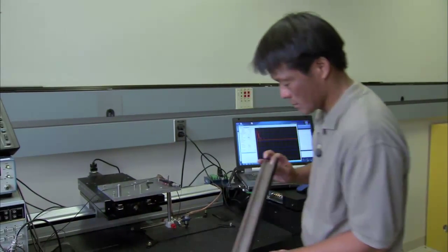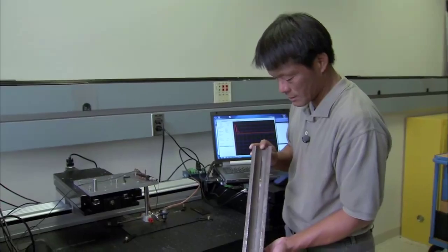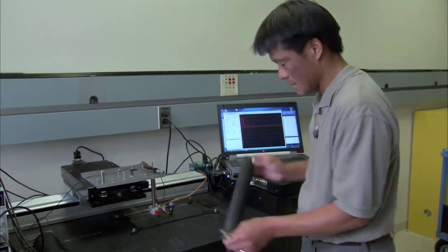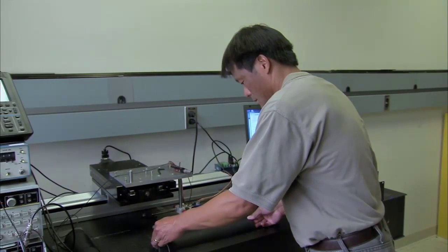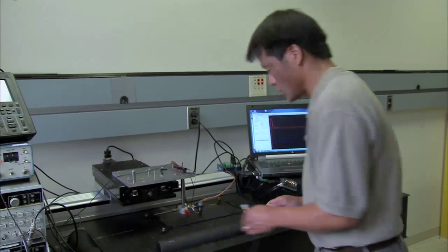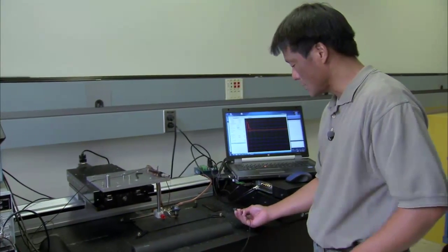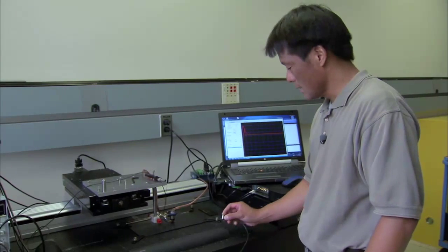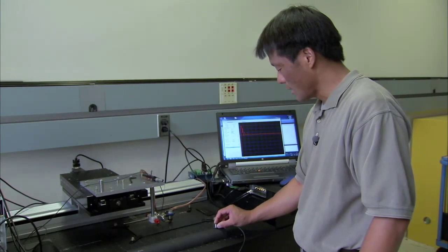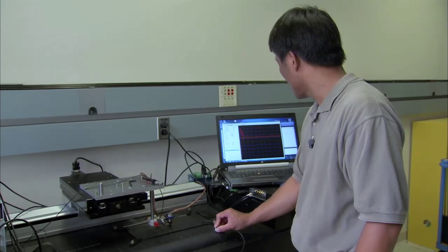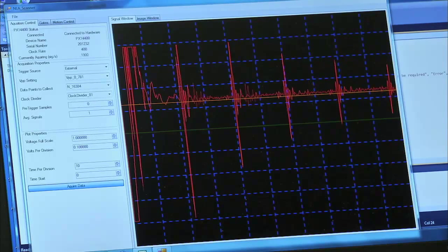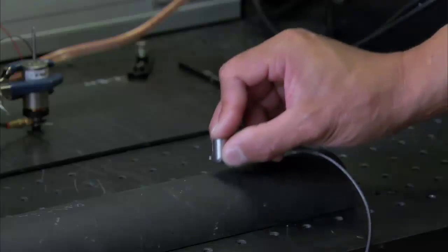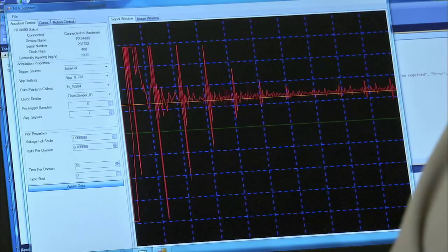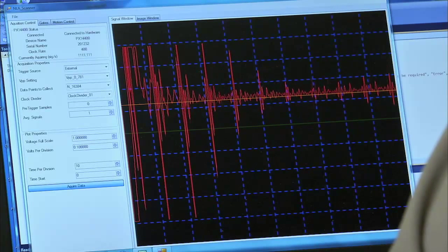Now I want to demonstrate this technology on a pipe with material loss inside, so that to simulate corrosion damage in the pipe. So if we take the transducer and solid couplant material and apply it in an area where there's no defect, you can see again the multiple echoes and the ring down effect. Notice the spacing. If I move the transducer over an area where there's a defect, you can see again the multiple echoes, but they're spaced closer together.